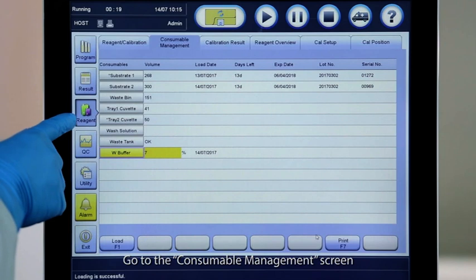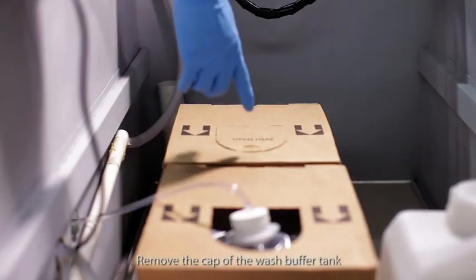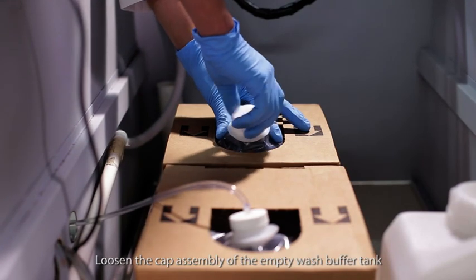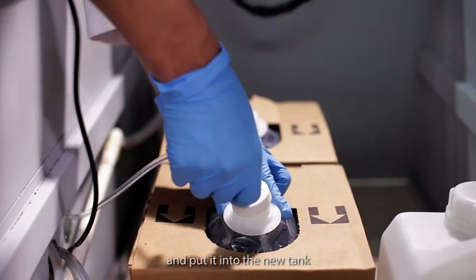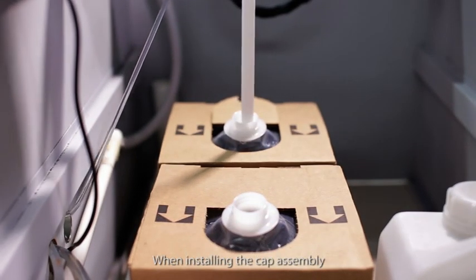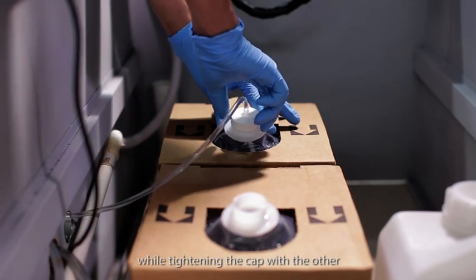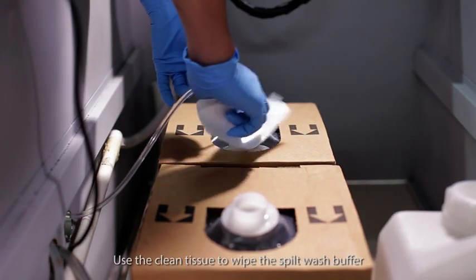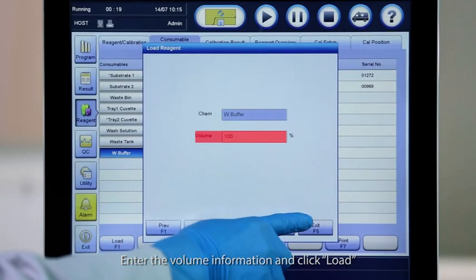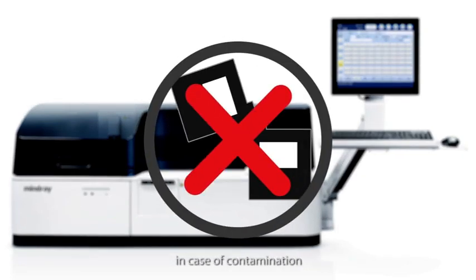Go to the consumable management screen. Open the reagent load screen of wash buffer. Remove the cap of the wash buffer tank. Loosen the cap assembly of the empty wash buffer tank and put it into the new tank. Do not contaminate the cap assembly. When installing the cap assembly, lift the tank mouth with one hand while tightening the cap with the other. Use a clean tissue to wipe the spilt wash buffer. Enter the volume information and click load. Do not pool the dead volume of the wash buffer in case of contamination.